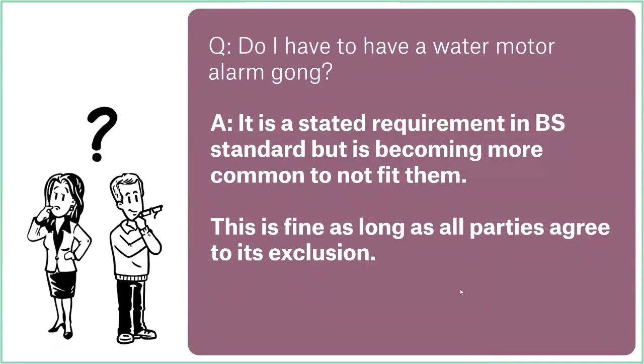If you've forgotten what a water motor alarm gong is, there's more detail in Sprinkler Talk 8, where I go through different types of alarm valves, and the water motor alarm gong is mentioned there. It's a water-powered bell. In honesty, it's not very useful these days. We're basically going to ignore it. We're going to be taking digital signals instead. So it is becoming more common to not fit a water motor alarm gong, which is obviously fine as long as all parties are signed off and happy that they're not going to be installed.